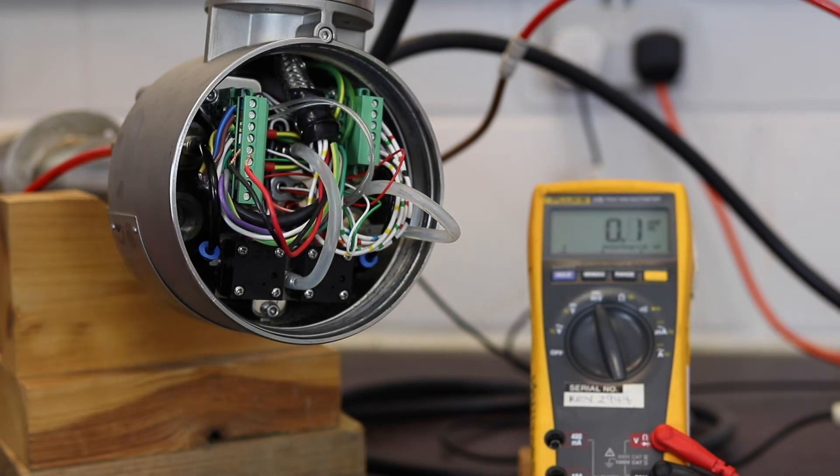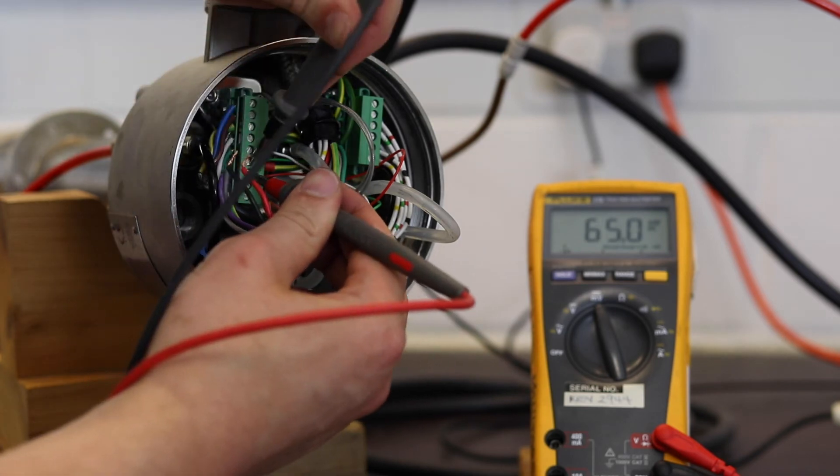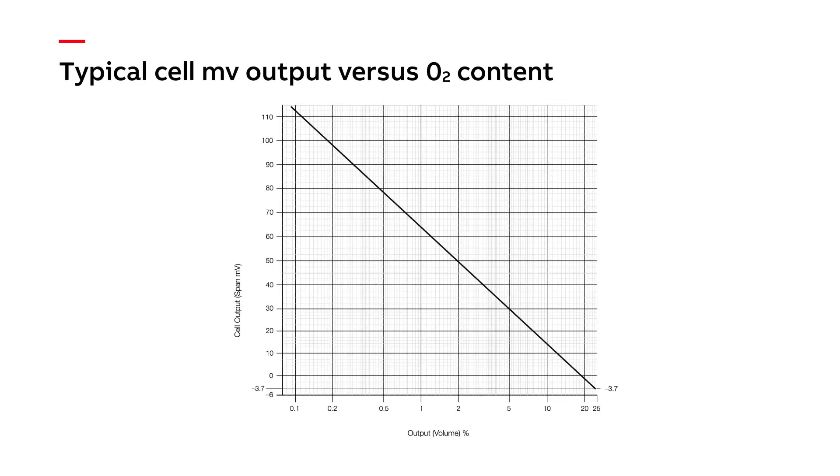If your probe has no auto-cal, we must manually open the test gas valve in the transmitter menu. Finally, we measure the millivolts across the red and black cell terminals and cross-check our results with the theoretical cell value in the maintenance guide. A typical output for one percent gas is around 65 millivolts, which is what I got from my cell. You can also repeat the test with compressed air, where you are looking for a millivolt reading somewhere around plus or minus two millivolts. If your reading is more than five millivolts away from the theoretical value, the cell may need to be replaced. If the reading is good, it is highly likely that the cell, heater and thermocouple are all working well.